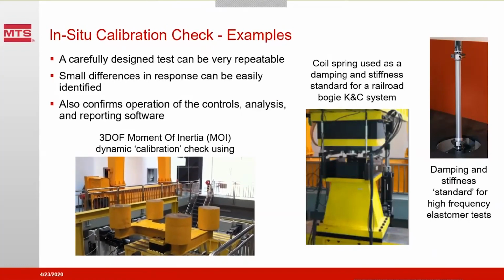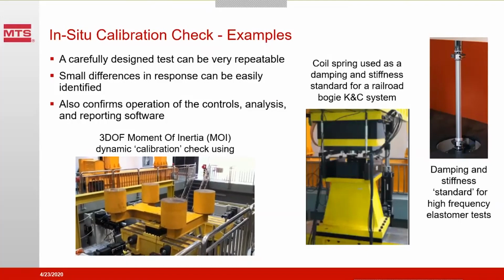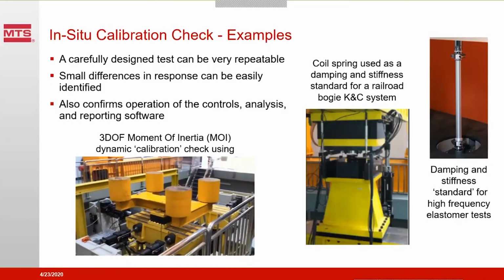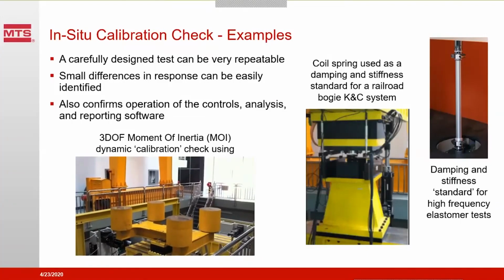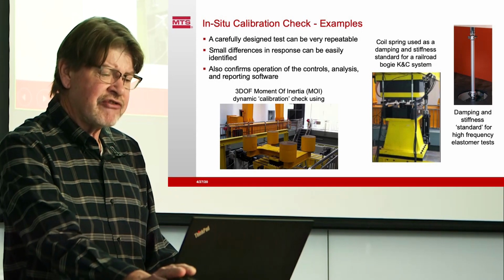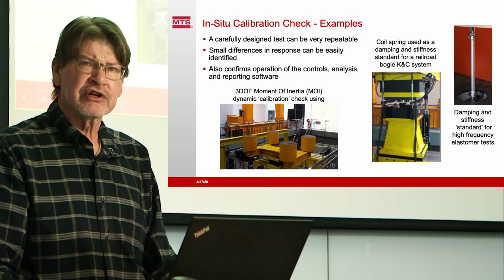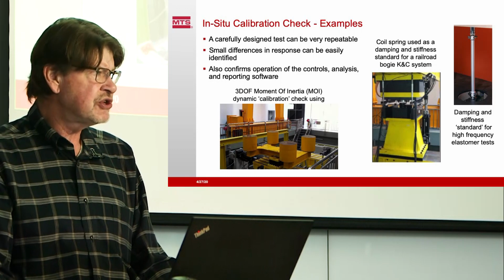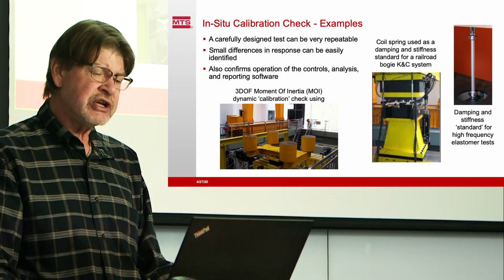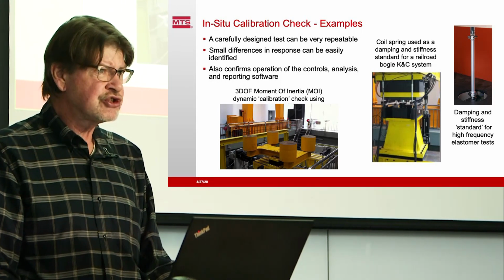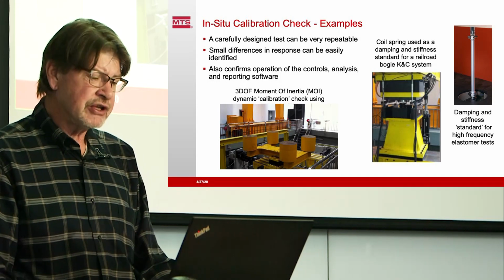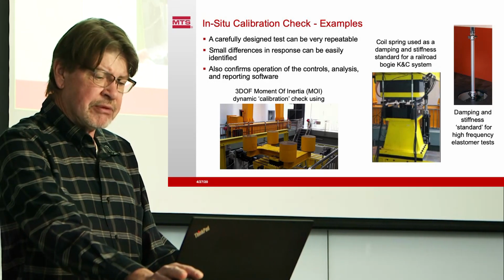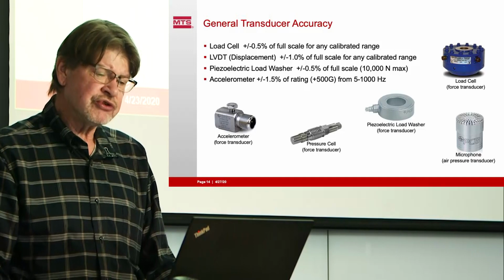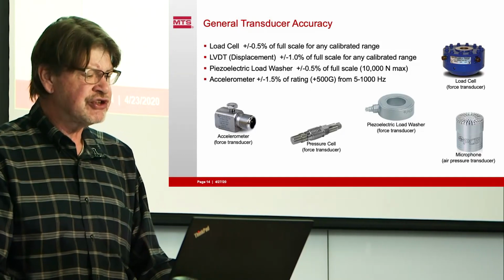Or maybe push against a spring or a damping and stiffness standard for an elastomer machine, such as we see over on the right. Those things have very repeatable stiffness and damping characteristics, so they can be inserted into the machine and used to check not only the machine and its transducers, but also the software and the connection paths and the analysis capability. General transducers are considered to have a certain accuracy.